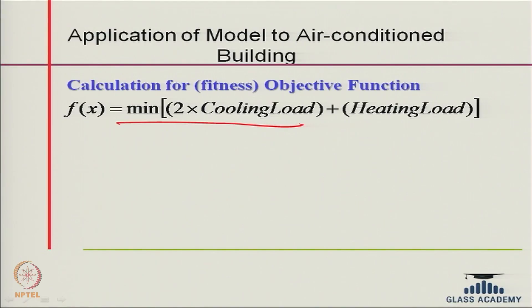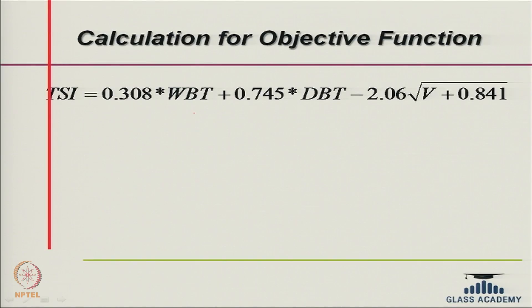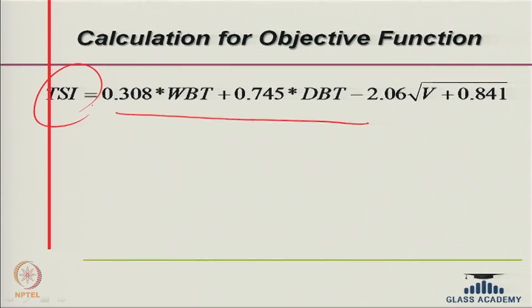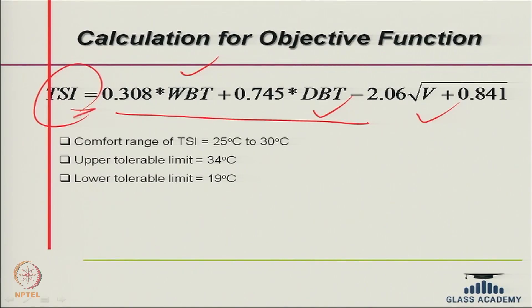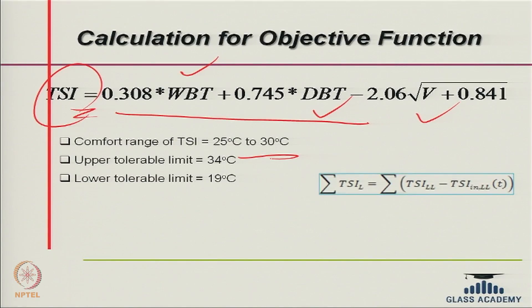The objective function to minimize is twice the cooling load plus the heating load, because heating is cheaper than cooling, which is why the factor of two is applied. You can also define a fitness function. Another approach is for naturally conditioned buildings: you can use a comfort index like the Tropical Summer Index specified in SP 41, which is related to wet bulb temperature, dry bulb temperature, relative humidity, and air velocity, and minimize the deviation from the comfort zone.